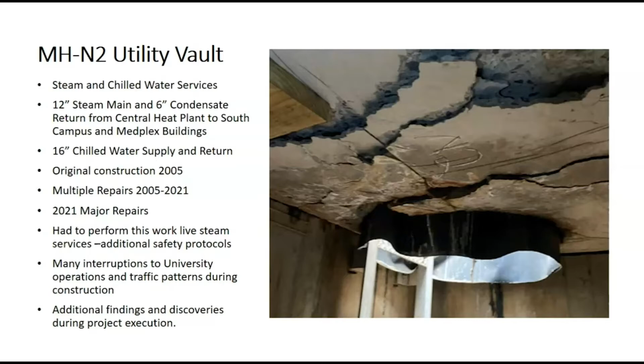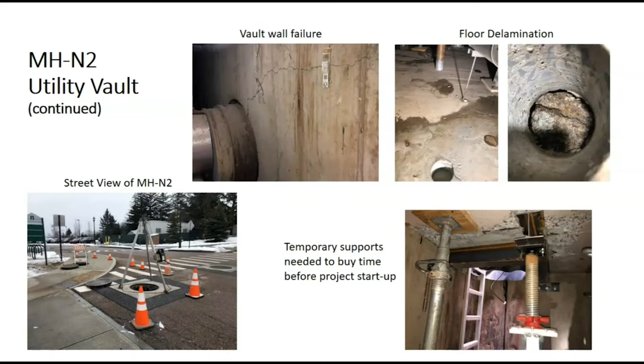After we noticed the spalling concrete, we took temporary supports and shoring and used that to support the roof, to buy us time to seek engineering consultants and get project specifications and drawings completed for the repair. During the engineering evaluation, we found additional vault wall failures and floor delamination of the concrete itself, and went out for bid and started the repair, and had additional discoveries of corroded sleeves, which you could see in the top right, which needed to be replaced. So we made additional modifications and put in new sleeves and seals for the project.